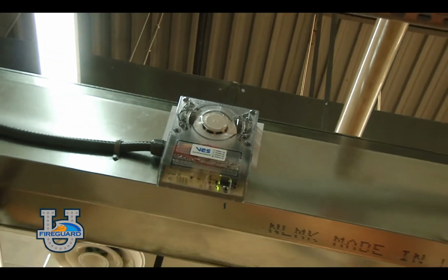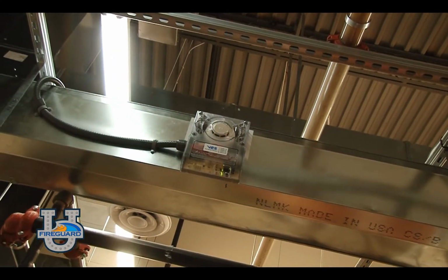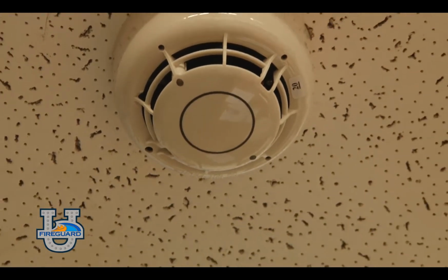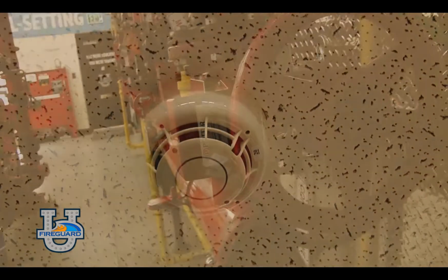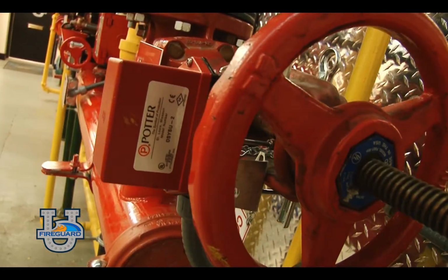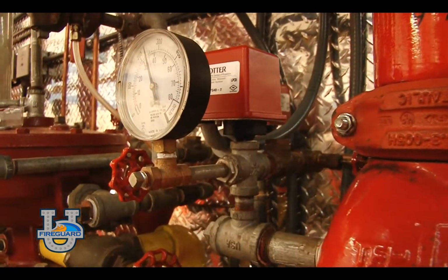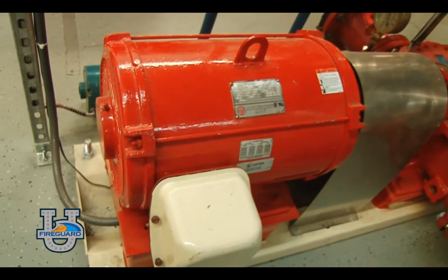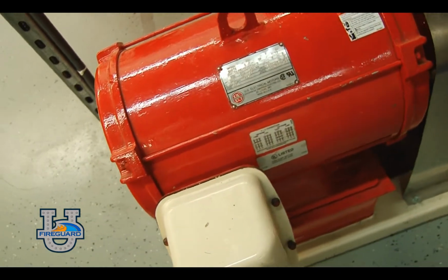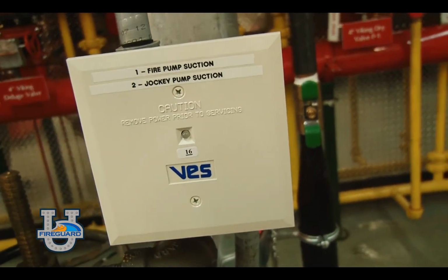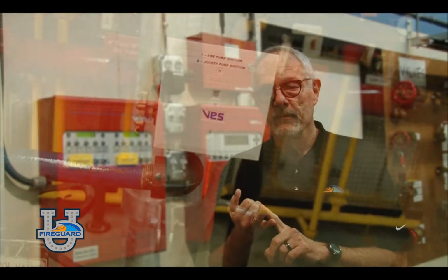It reacts to a high concentration of airborne particles. Carbon monoxide detector reacts to high levels of carbon monoxide. A sprinkler valve tamper switch. It reacts when a fire sprinkler system valve begins to close. A low air switch on the fire sprinkler system. Also, fire pump off normal conditions will trigger supervisories. This could be a loss of power, a phase reversal, or a fire pump running.